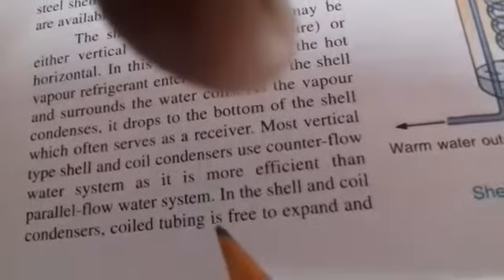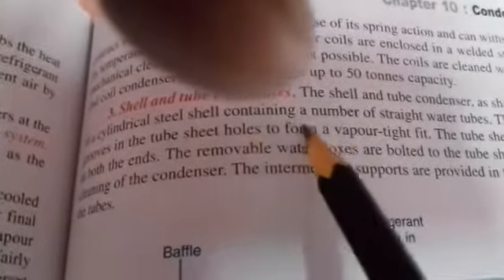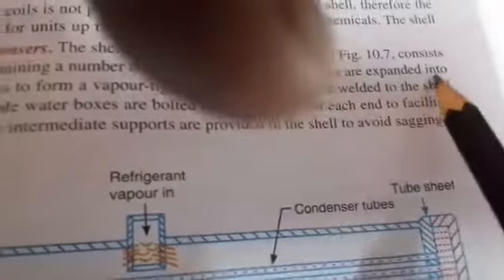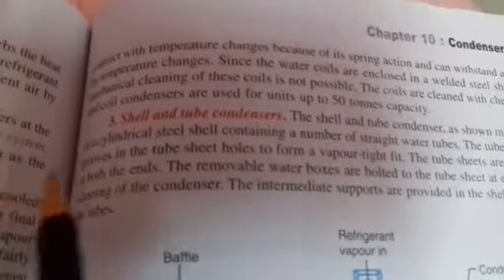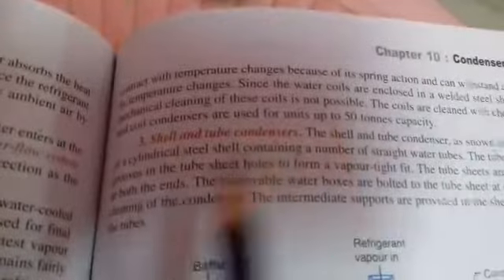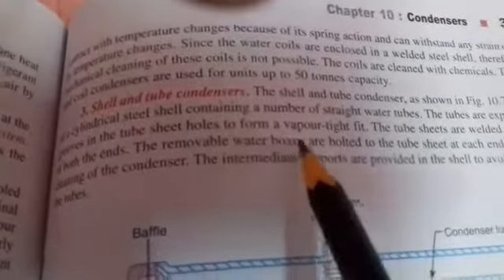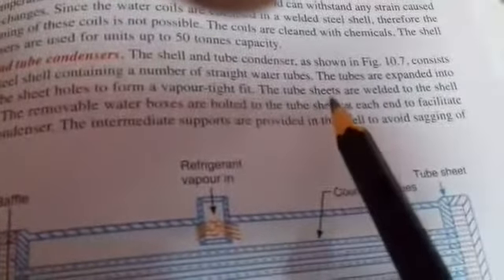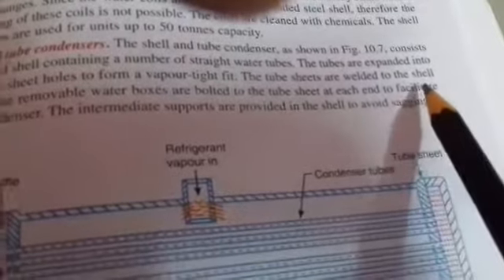The shell and tube condensers, as shown in the figure, consist of cylindrical steel shell containing a number of straight water tubes. The tubes are expanded into grooves in the tube sheet holes to form a vapor tight fit. The tube sheets are welded to the shell at both the ends. The removable water boxes are bolted to the tube sheet at each end to facilitate the cleaning of the condenser. That's all. Thank you.